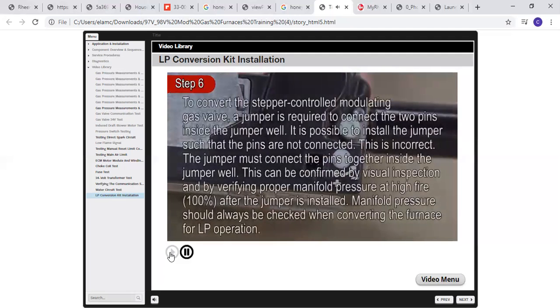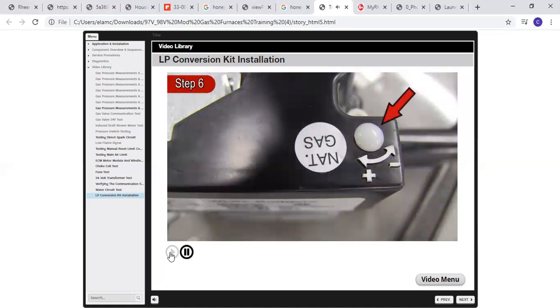Step 6. Note, to convert the stepper-controlled modulating gas valve, a jumper is required to connect the two pins inside the jumper well. It is possible to install the jumper such that the pins are not connected. This is incorrect. The jumper must connect the pins together inside the jumper well. This can be confirmed by visual inspection and by verifying proper manifold pressure at high fire 100% after the jumper is installed. Manifold pressure should always be checked when converting the furnace for LP operation. The jumper well is located next to the adjustment well with the plus and minus text and two-headed arrow, and will be covered by a sticker or label.